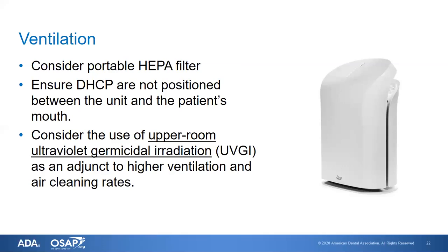UVGI systems have to be done carefully, and you have to understand the airflow dynamics in the office, so you would probably want to consult with somebody with expertise before installing them. The number of air exchanges per hour can also affect the efficiency of UVGI — if you have more air exchanges per hour, the particulates don't have as much contact with the UV and it may not be as efficient.